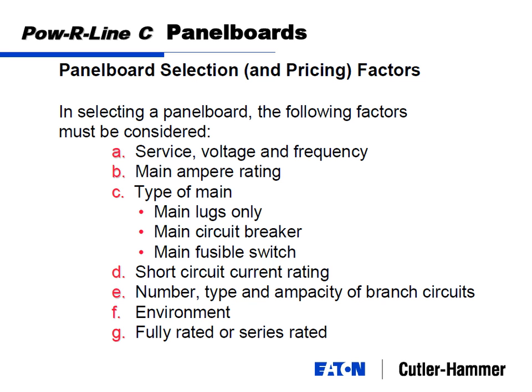So if I built a facility and I happen to be running a sand plant and I've just got a little shed out next to the sand plant that has a panel board, you maybe want to consider a dust type one so sand doesn't get into the panel board. What does environment mean inside a panel board? It means countdown to failure. Whether that environment is rain or dust, or in the next case, certain gases can come into play.